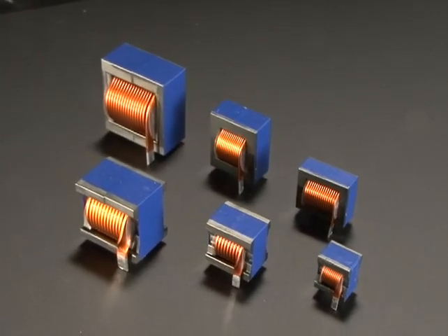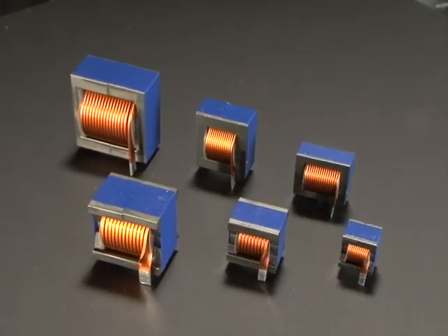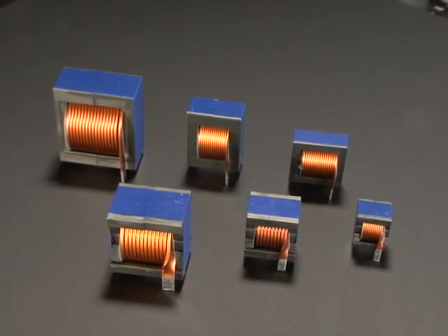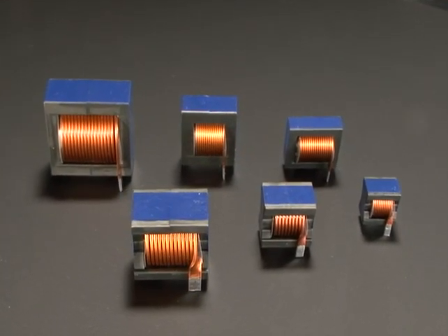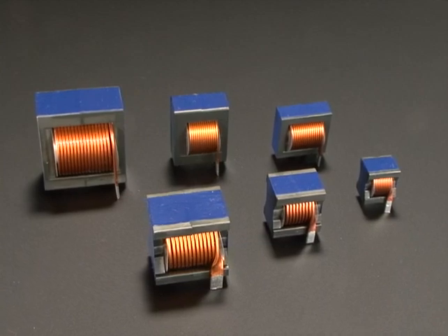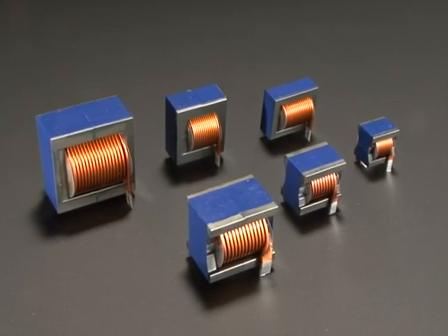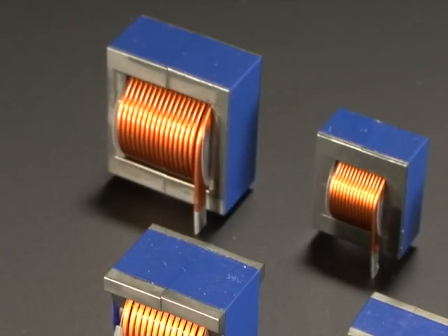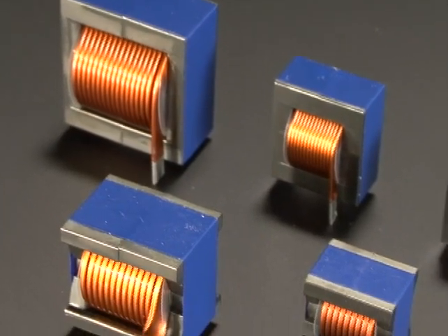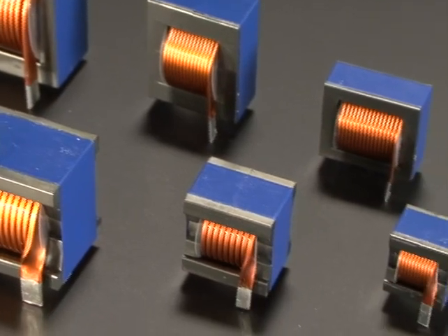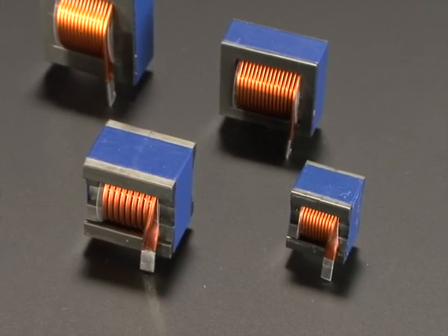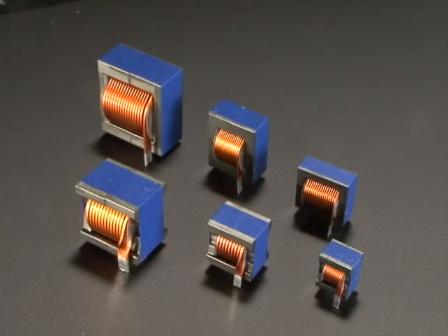Compared to resistors and capacitors, inductors are less susceptible to damage. When they are damaged, it is often difficult to detect from external appearance alone. Insulation film applied to the coil will deteriorate in environments with high ambient temperatures. In the worst case, the coil short-circuits and is no longer capable of functioning as an inductor. Coils are found in the motors of seawater and freshwater pumps, and their insulation is weakened by the absorption of moisture. The main purpose of measuring insulation resistance using a megger is to check for coil insulation degradation.